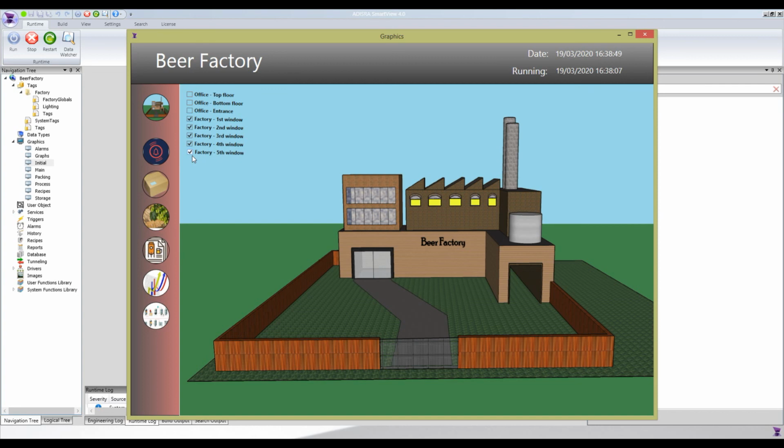And that's it. I just wanted to show you how to configure the checkbox, and of course this is just a demo. In the real life you would have to use the same tags that we used on the checkboxes and on the IsVisible property to also communicate to probably a PLC using OPC, or maybe a driver using a specific protocol to get the information and actually turn on and turn off the lights. But since this is just a demo, I'm not creating any communication, and maybe in the future we can do it using a driver. Okay?